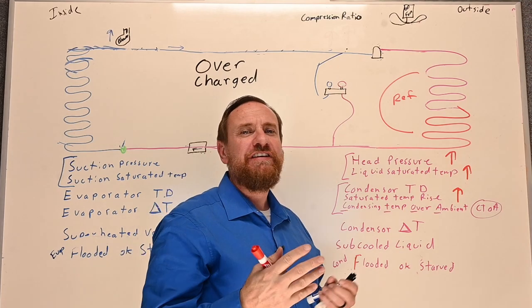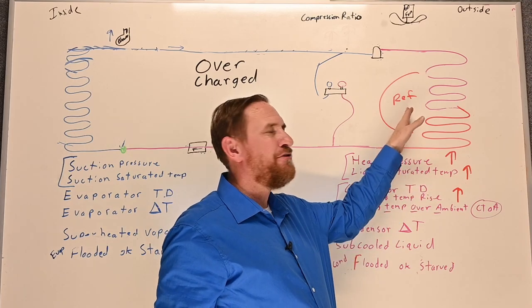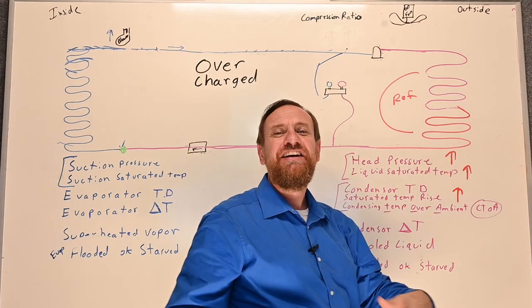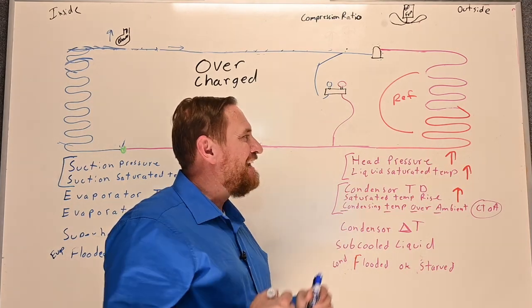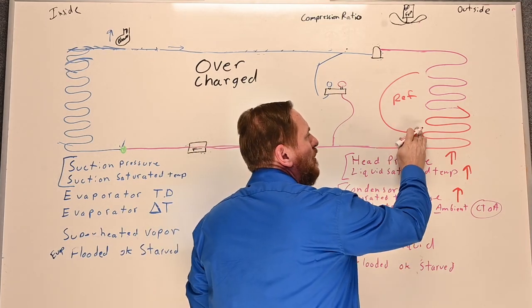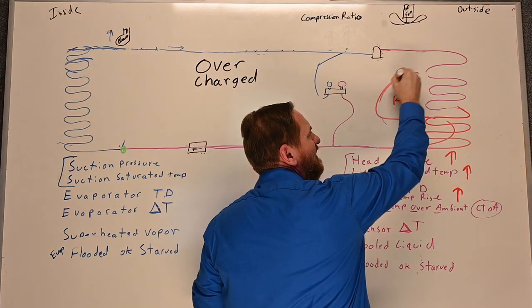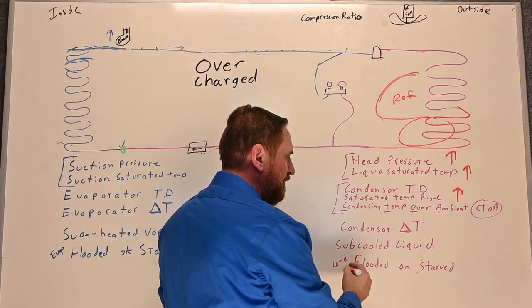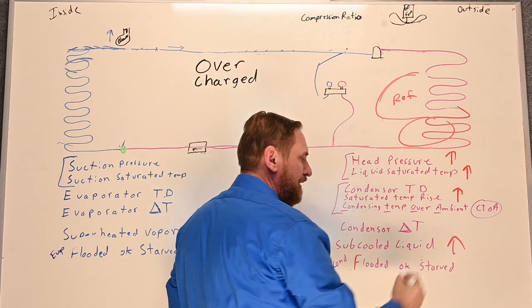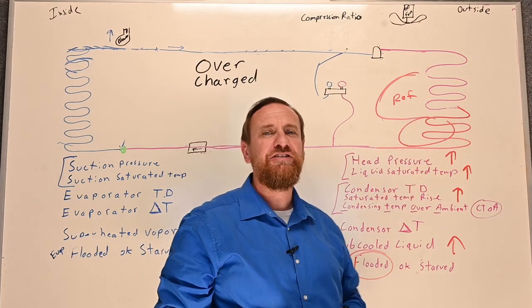Let's say we're designed for a 10 to 15 degree temperature difference. As we have more and more molecules, the pressure goes up, the saturated temperature goes up — now maybe we have a 30 degree temperature difference between the refrigerant and the air. That's a big important factor. We also have more refrigerant in the condensing unit, so we end up with more sub-cooled liquid. That pushes our saturation down to a smaller area, so our sub-cooling starts to go up, giving us a flooded condensing unit.